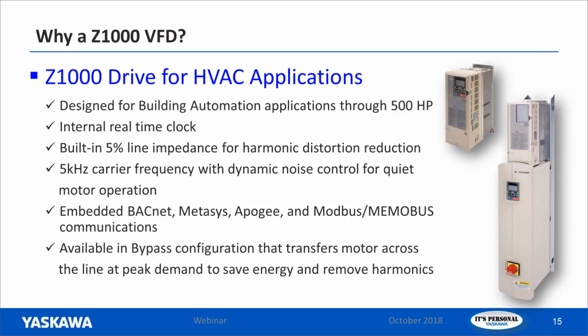However, the higher carrier frequencies are not good for the motor. Motors prefer lower carrier frequencies. They'll last longer, run cooler, and whatnot. But the problem is, once you get below 8 kilohertz, we're getting into the human ear territory, and you start hearing the whining of the motor. Well, we've developed this drive to be able to run at 5 kilohertz carrier frequency, but with the dynamic noise control that we have built in, we are still able to achieve the quiet motor operation. So this is a pretty good feature.